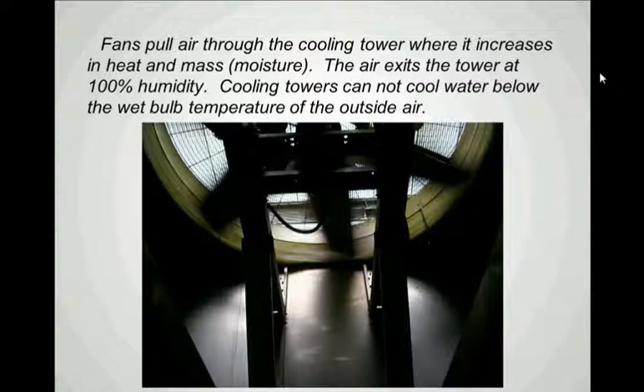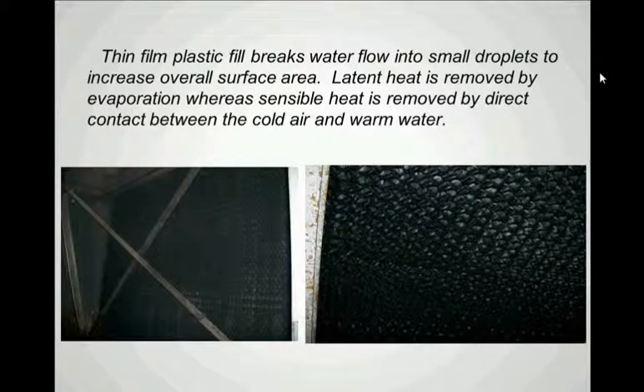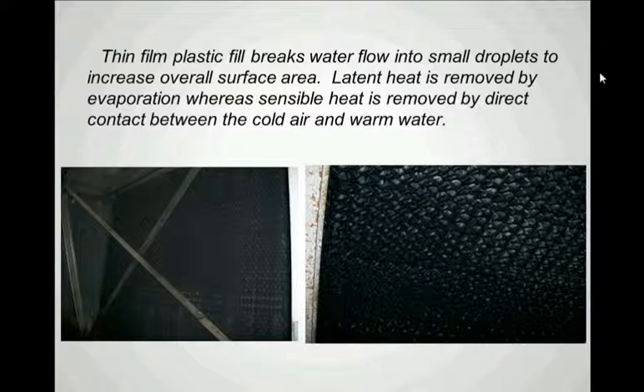Here's a closer view of the cooling tower fill. We're inside the cooling tower and as you can see, this plastic fill has a honeycomb appearance — often thought of as being like the corrugations in a piece of cardboard. The water that flows down through the fill is broken up into thin films or droplets to increase the surface area of the water, giving maximum exposure of the water to the air as it flows through the cooling tower, which in turn improves the overall efficiency of the cooling tower.